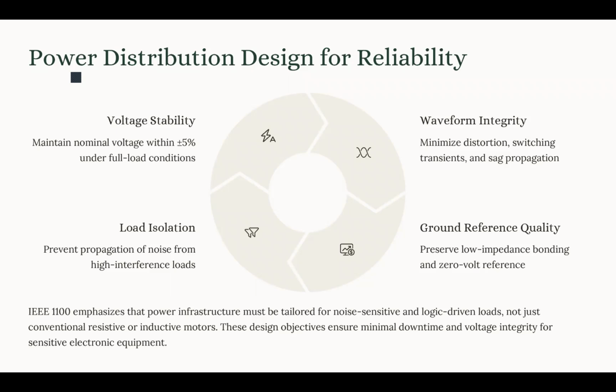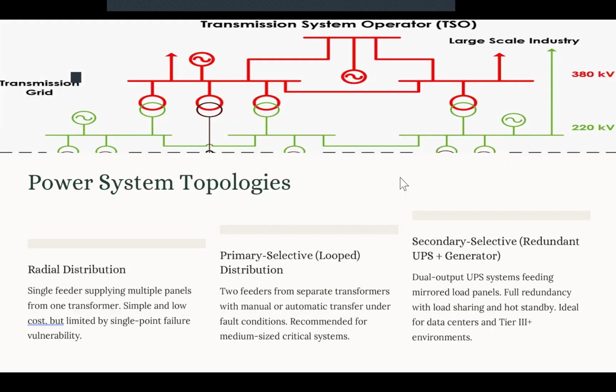Now, to do that, we could have several topologies in our power system. Basically, this power distribution topology determines the reliability and the fault tolerance and the availability of the power. And as we mentioned, the IEEE classifies those power distributions mainly into three main topologies: radial distribution, primary selective distribution, or secondary selective distribution. Now let's talk about those in detail.